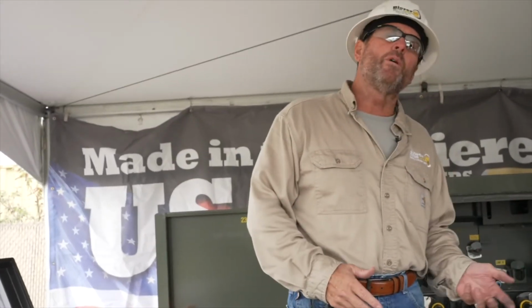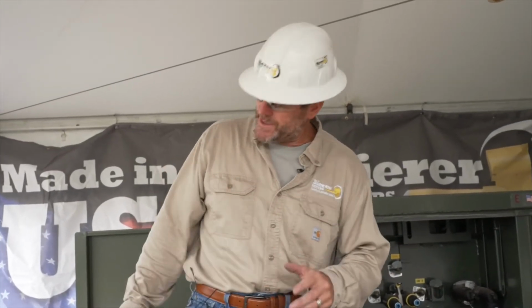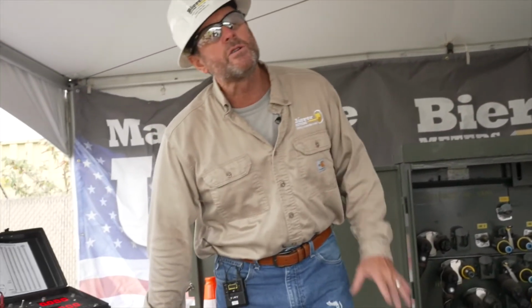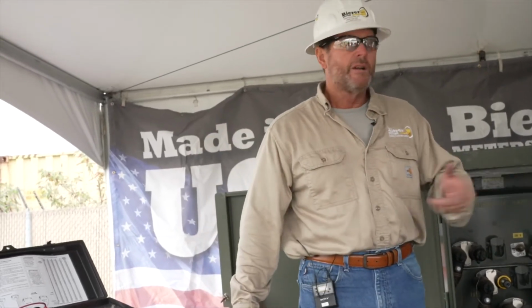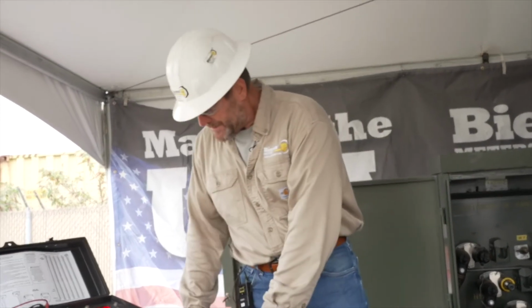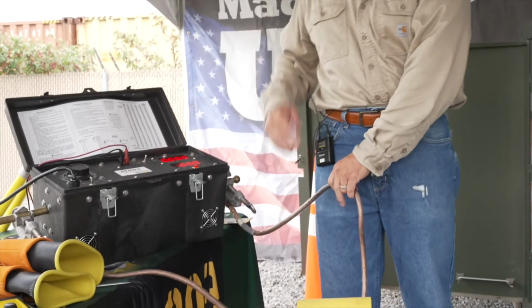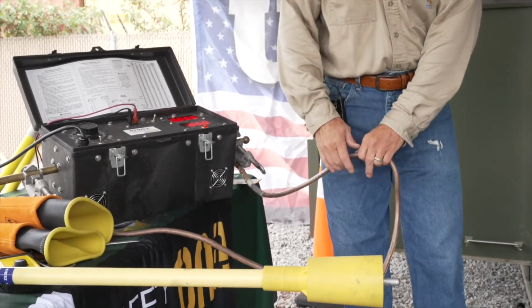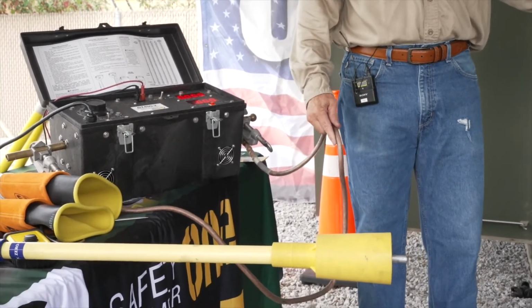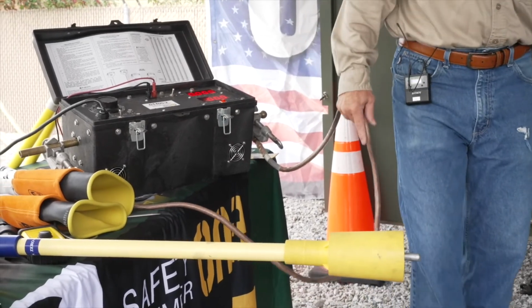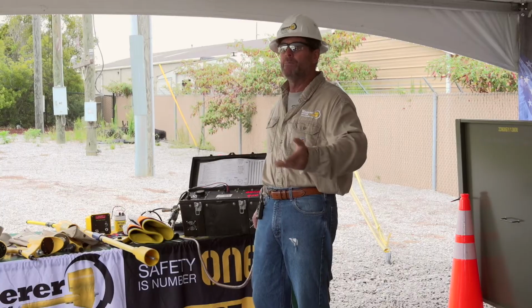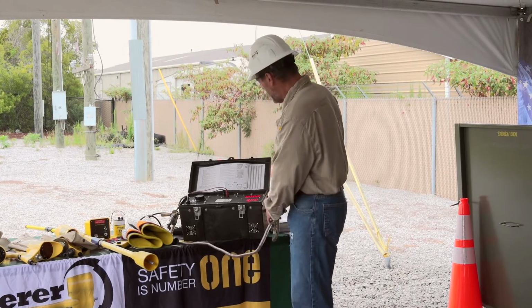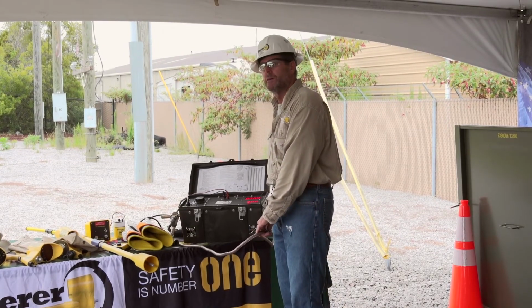Some folks test every 18 months, a few every 24 months, which I think is way too long. Most folks that electrically test their TPGs do it every year. So verify that your date stamp is in compliance with that once-a-year, or whatever, testing program. You could be out doing storm restoration, get called out, and get skipped, so verify that you did not get skipped.